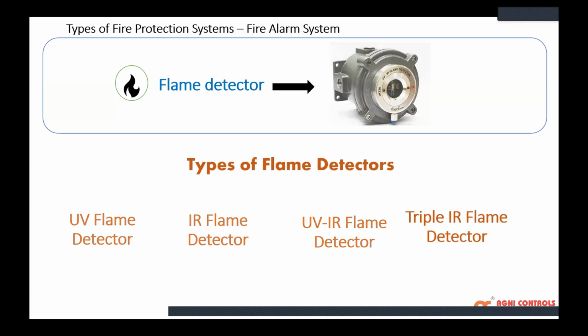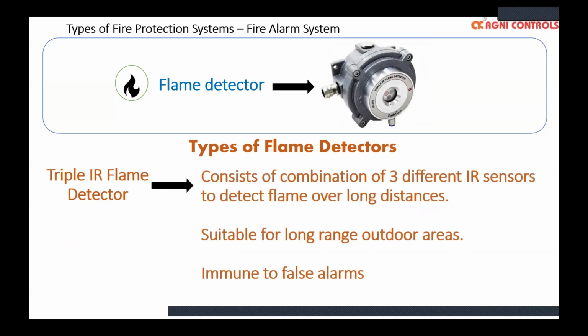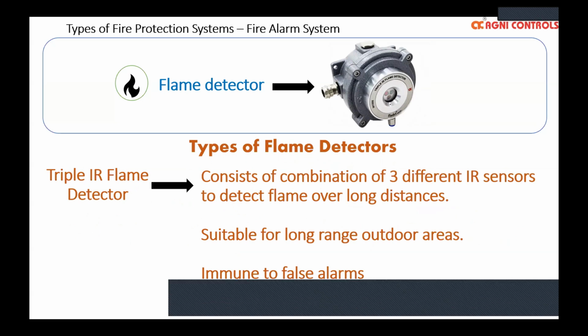Finally, the multiband detectors, or the triple IR flame detector, consist of three different types of IR sensors of various bandwidths, and it conforms to the spectral range of the flaming fire. These detectors are suitable for outdoor applications and long range distances. For detection capability of more than 50 meters, these detectors are more suitable. And these detectors are extremely immune to false alarm sources.